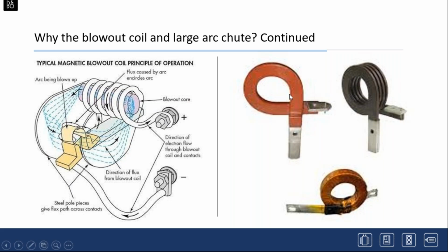To give you an idea what a blowout coil looks like, here would be a blowout coil that was made of wire. It could be anything from a very small number 12 to a number 8. When you get into bigger currents, here is a blowout coil made out of ribbon and just a single bar or complementary. So this is what a blowout coil looks like. And you will find a lot of reference in DC devices to the blowout rating. The blowout rating has to do with the force that is established here when you're actually interrupting the arc.